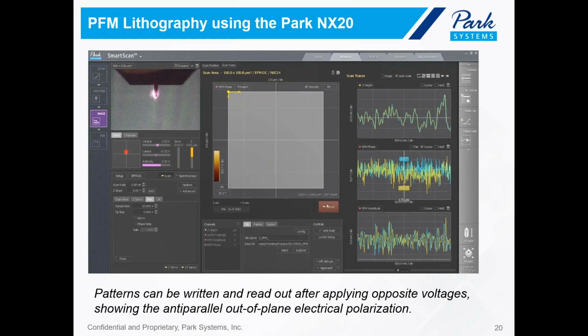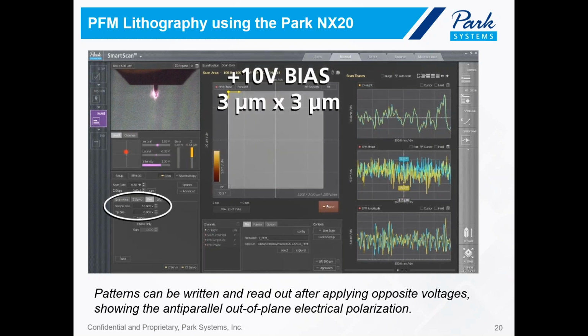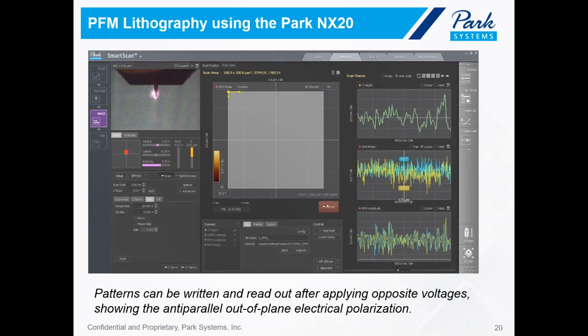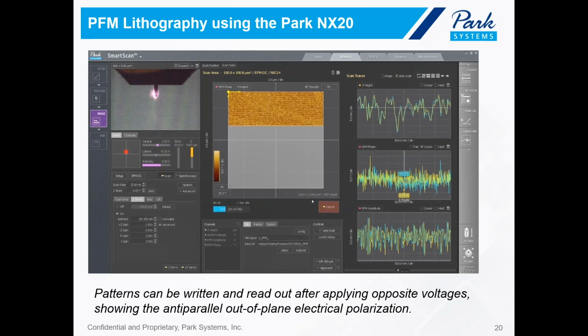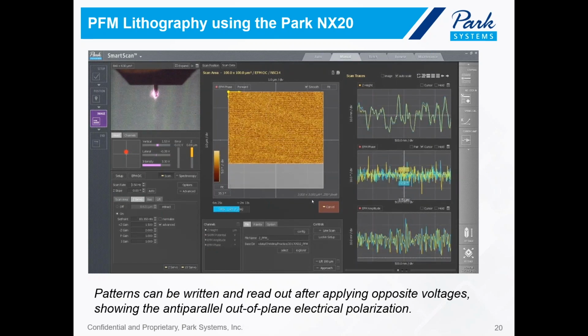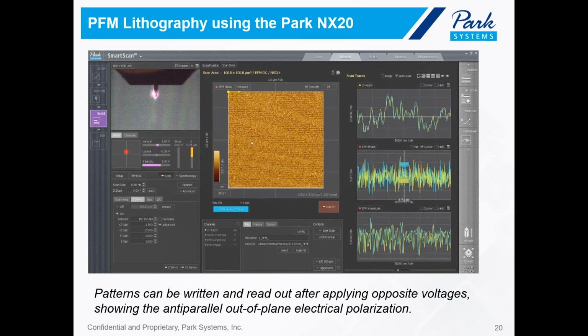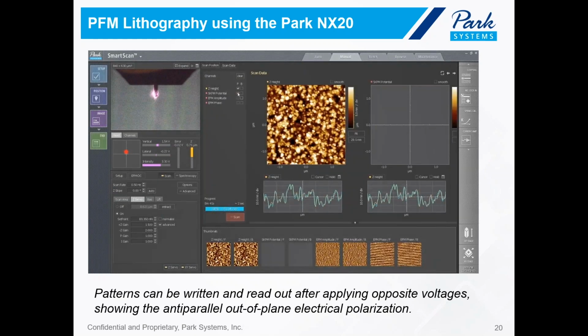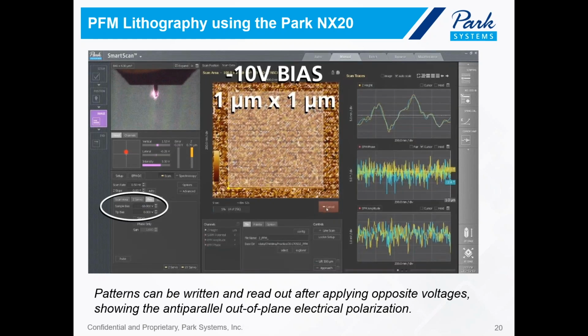So to start, we input a sample tip bias here from the software, positive 10 volt, and we scan the 3 micron by 3 micron region. So here is the scan. This is a phase channel, so we don't expect to see much. But here is the topography channel, and you can see we monitor the topography and phase separately. And next, we zoom in.